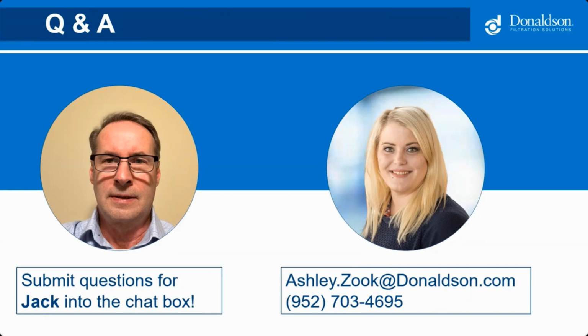And just because you're just now talking about that DHA, one of the questions says, if a client is not super technical and not willing to do the dust hazard testing, what resources do you use as a rule of thumb? Well, that's a good question. You have to be very careful on your answer, because again, it's a litigious world. So you definitely have to make sure the customers work with an AHJ if the dust is deemed to potentially be combustible, because you and your customer are not AHJs, authorities having jurisdiction. There's 4 entities that I'm aware of in the United States that could be potentially classified as such. So having said that, you want to make sure that they're on board with whatever solution is proposed, because all you can do is provide potential solutions.